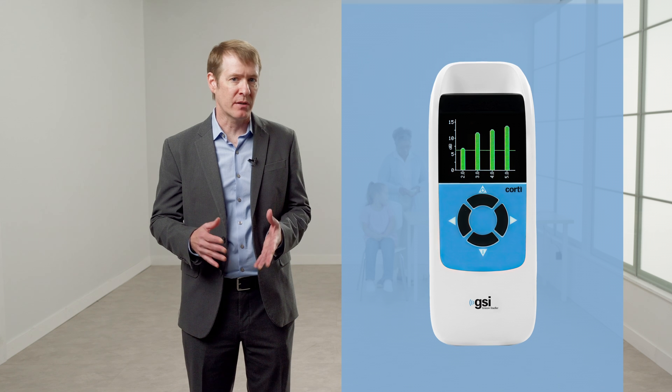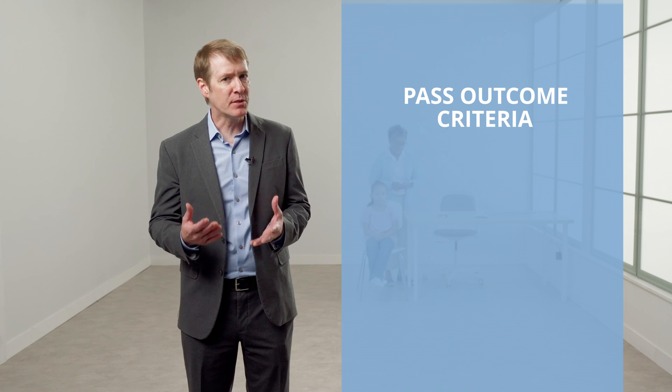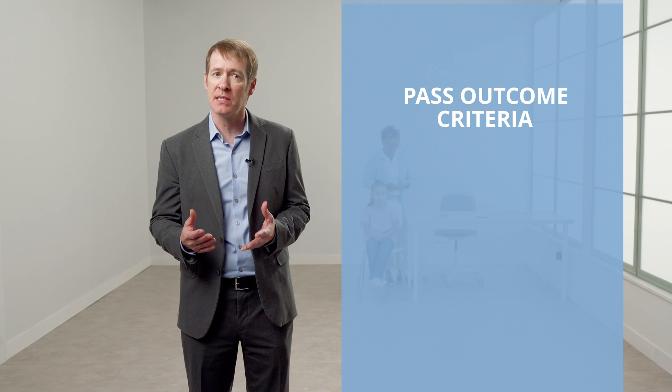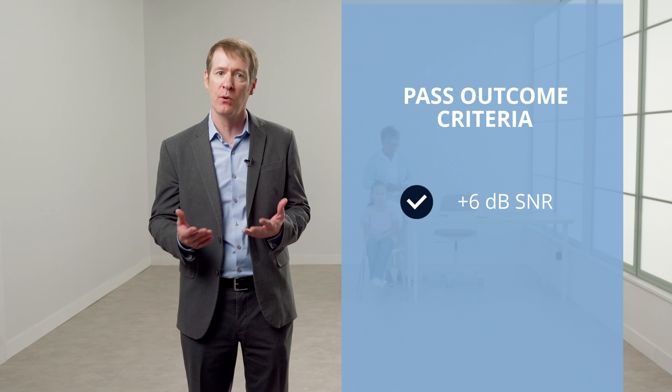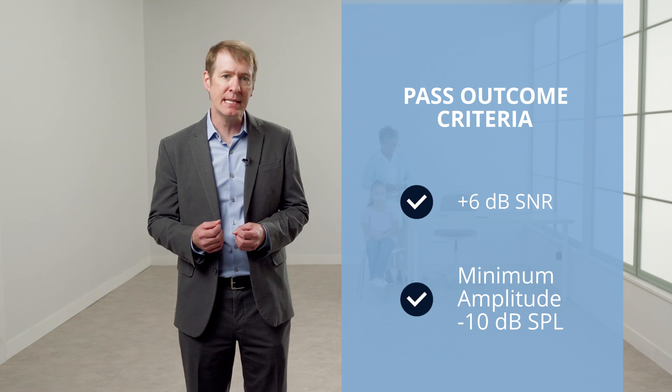During the OAE test, the results will display in real-time as either signal-to-noise bars or a value graph on the display screen of the Corti. For screening protocols, the device automatically analyzes the OAE and determines whether the screening result is a pass or a refer. There are two criteria for a pass outcome: first, the amplitude of the DPs at each of the four test frequencies must be at least 6 dB above the noise floor; and the DP minimum amplitude must be greater than minus 10 dB SPL. A pass or refer message will appear on the display screen when screening is complete, and test results are automatically stored.